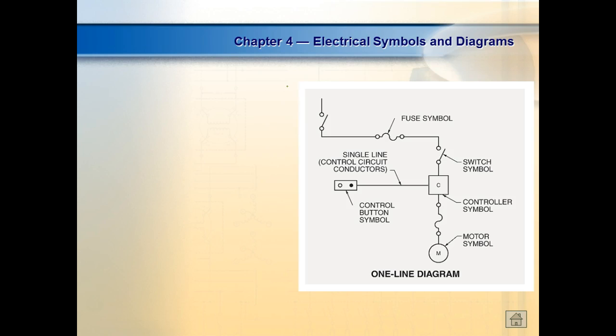This is what they call a single wire drawing, a one line drawing. What this does is they take for granted that you as an electrician or electronic repairman knows everything's got to have two wires going to it. One of them would be what we call the common. So they don't use a symbol for the common, they just don't draw it. So on a one line diagram, they do not draw the common. Is it there? Yes. If it wasn't there, nothing would work. And the less stuff we leave out of the diagram, the more complex, the less complex it gets. So they take for granted you know that.